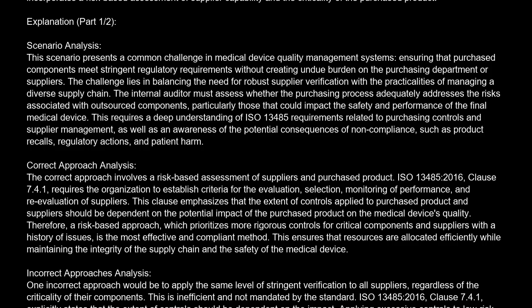One incorrect approach would be to apply the same level of stringent verification to all suppliers, regardless of the criticality of their components. This is inefficient and not mandated by the standard. ISO 13485:2016, Clause 7.4.1 explicitly states that the extent of controls should be dependent on the impact. Applying excessive controls to low-risk suppliers is a misinterpretation of the standard's risk-based philosophy.